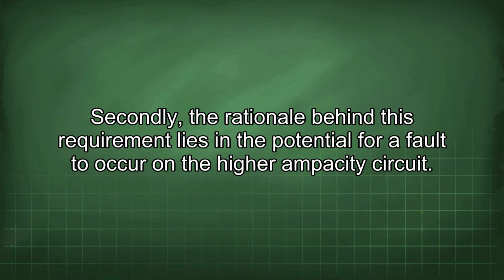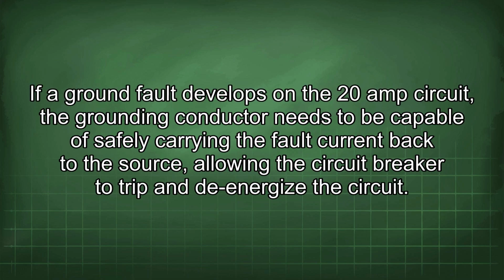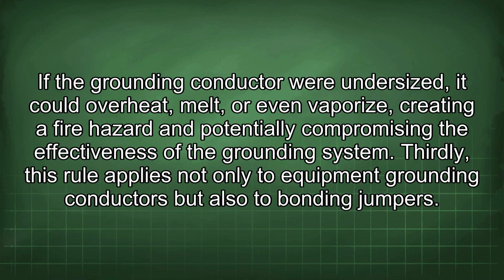Secondly, the rationale behind this requirement lies in the potential for a fault to occur on the higher ampacity circuit. If a ground fault develops on the 20 amp circuit, the grounding conductor needs to be capable of safely carrying the fault current back to the source, allowing the circuit breaker to trip and de-energize the circuit. If the grounding conductor were undersized, it could overheat, melt, or even vaporize, creating a fire hazard and potentially compromising the effectiveness of the grounding system.